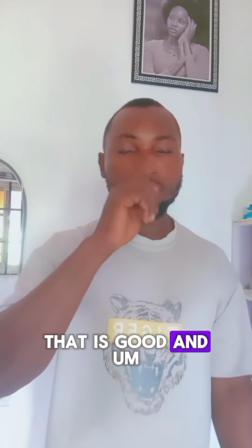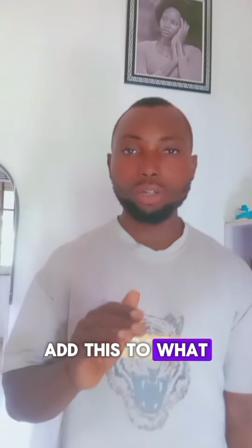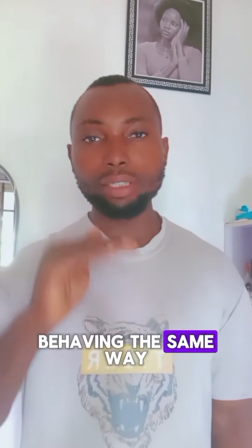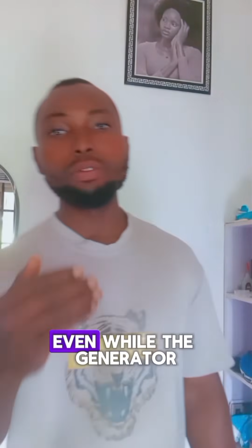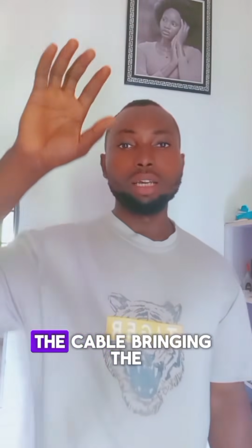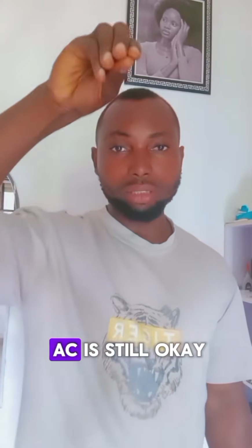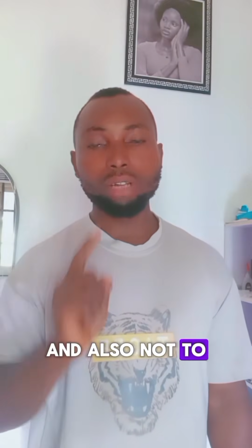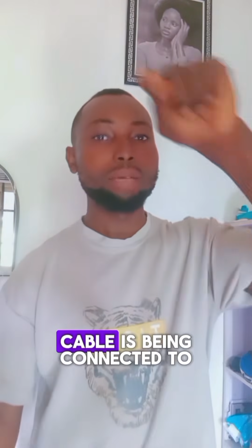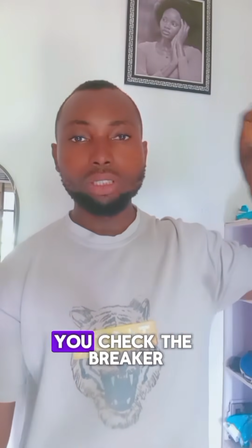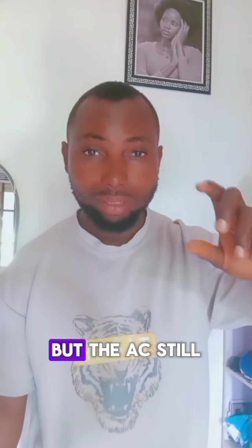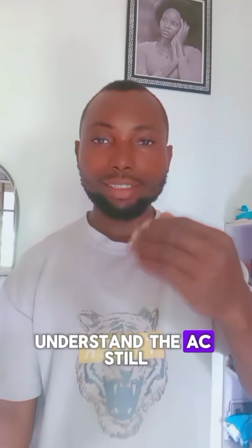Let me add this to what we've been discussing. If you check all these factors and your AC is still behaving the same way, still peaking and dropping, even while the generator is okay, the cable linking the home and the generator is okay, the cable bringing power to the AC is okay, and you've also checked your breaker in the distribution board and it's okay, but the AC still keeps behaving like that...